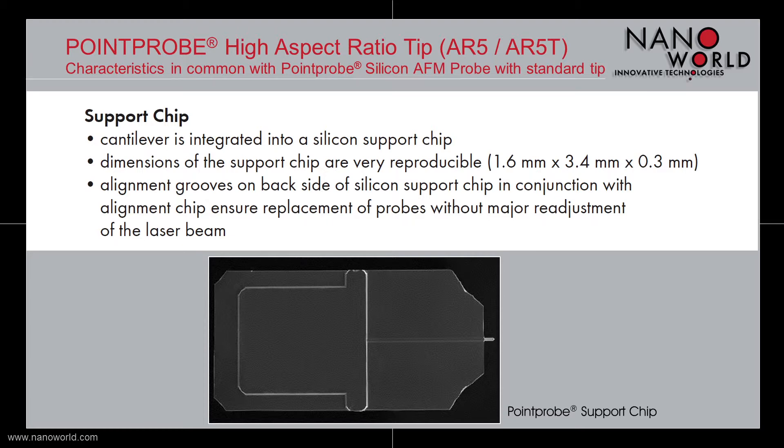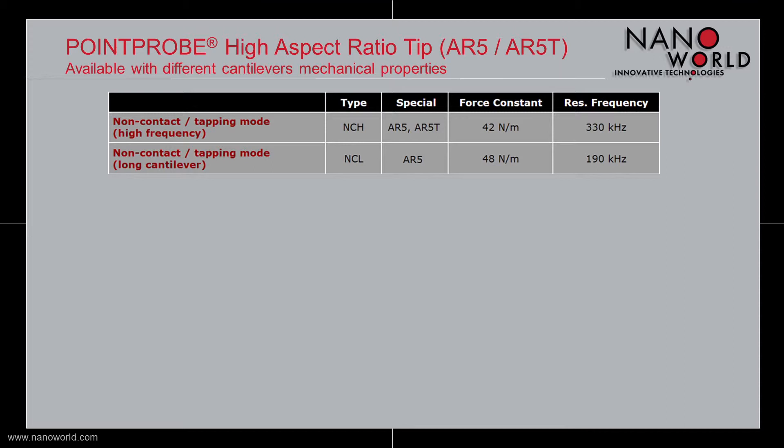3.4 mm long and 300 µm thick. The Pointprobe High Aspect Ratio Tips are available with different cantilevers for non-contact measurements.